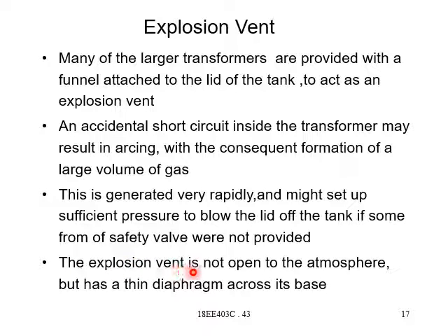The explosion vent is not open to the atmosphere but has a thin diaphragm across its base. If it were exposed to the atmosphere, again moisture would get in and the transformer oil would get polluted and form sludges and all those things. So this is not directly open to the atmosphere but has a thin diaphragm across its base. This thin diaphragm acts to prevent moisture from entering the transformer tank.